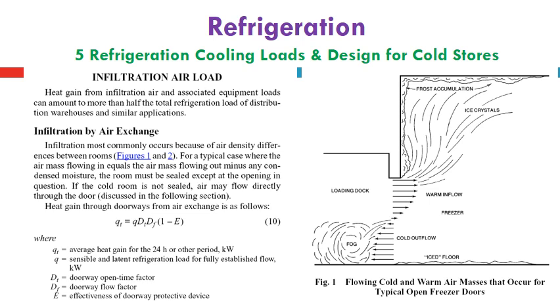And on the other side, on the upper side, the warm air infiltrates inside the refrigerated space and can generate a lot of disturbance inside the refrigerated space and additional internal load due to this door opening during evacuation and filling of this refrigerated space. So heat gain from infiltration air and associated equipment loads can amount to more than half the total refrigeration load of distribution warehouses and similar applications. So it should be considered carefully.